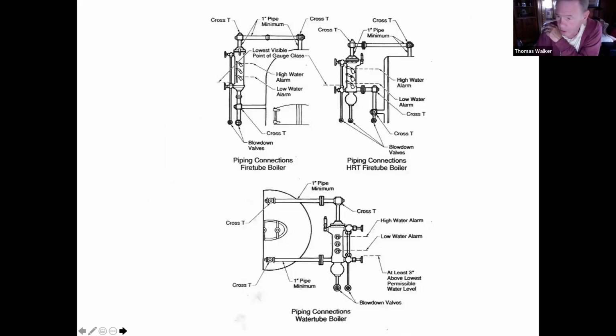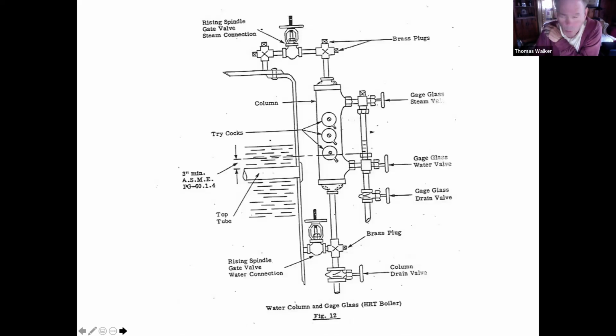Water columns and gauge glasses, pretty self-explanatory. The water column is attached to the boiler. It's always attached with cross tees. That allows us to clean it out and inspect it without removing the water column from the boiler. If you have valves going to the water column, they have to be the type of valve that indicates its position.